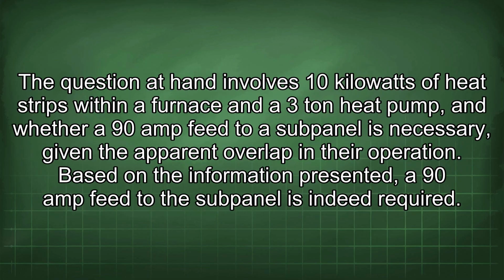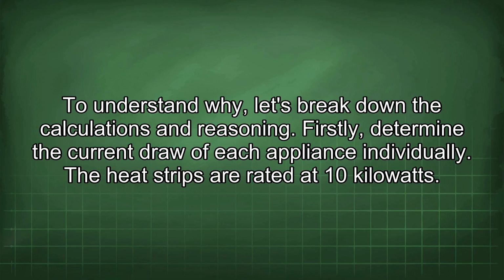The question at hand involves 10 kilowatts of heat strips within a furnace and a 3-ton heat pump, and whether a 90 amp feed to a subpanel is necessary, given the apparent overlap in their operation. Based on the information presented, a 90 amp feed to the subpanel is indeed required. To understand why, let's break down the calculations and reasoning.